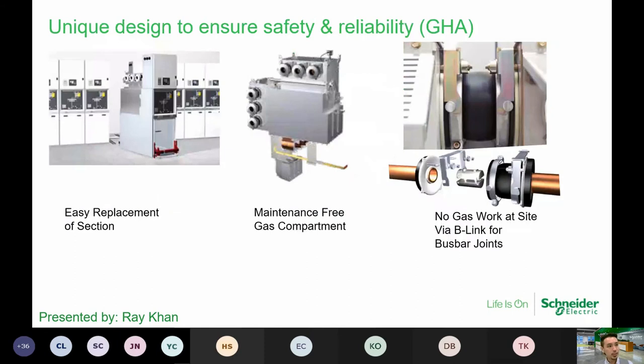So over in here, pretty much these are the key important features of a GHA. They focus on giving the client an easy replacement concept. So within about 4 to 5 hours, you can have your replacement done. And most importantly of all, it doesn't require gas work on site. So in the second one here, you can see that it's a maintenance-free compartment. All the high voltage components are installed in the compartment and it's fully gas filled. All right, so the gas tank is made of chromium nickel steel, and it has also been tested according to IEC 62271, which means it's leak proof, right? So the replenishing of gas is not needed unless the tank is damaged. All right, so on the right end here, you can see there's no bus bar gas work on site via the B link for the bus bar joint.